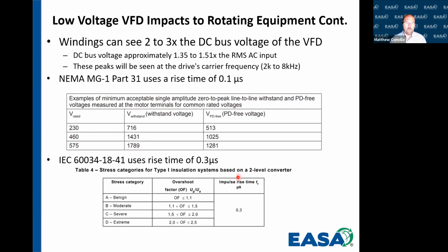And if we're at 200% of that, we're at 1,440 volts. So as you can see, with a standard insulation system here that meets Part 31, if we have a 720 volt DC bus, we might be over the withstand voltage that can be seen if we don't have the appropriate output filtering. And it's also asking for us to be partial discharge free at 1,025 volts. And it wants us to have everything be able to withstand this on a time base, or a rise time, of 0.1 microseconds.